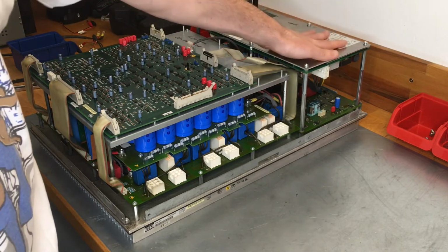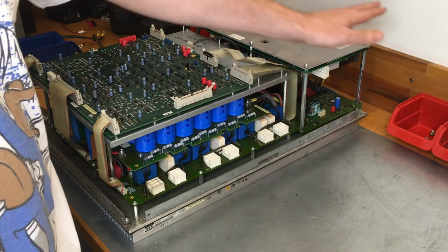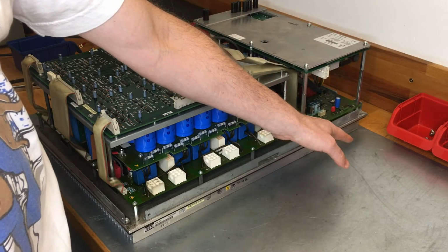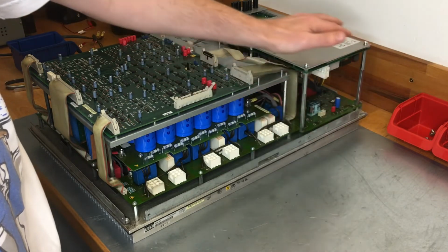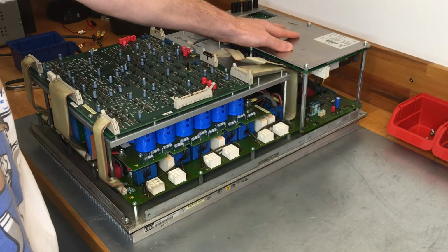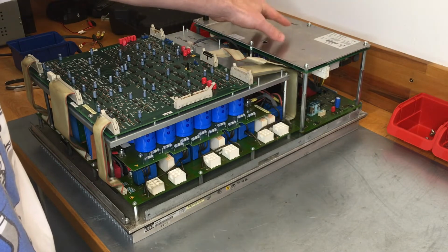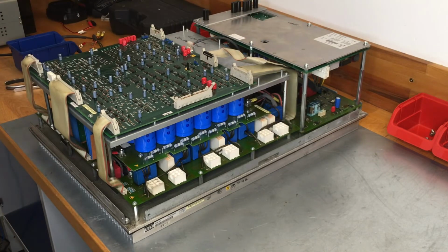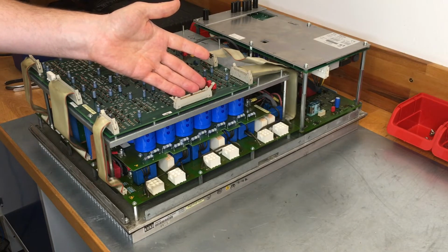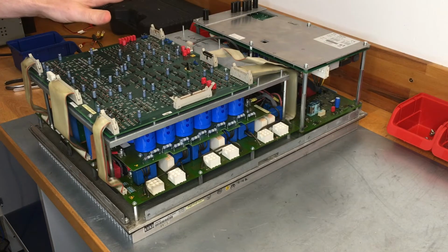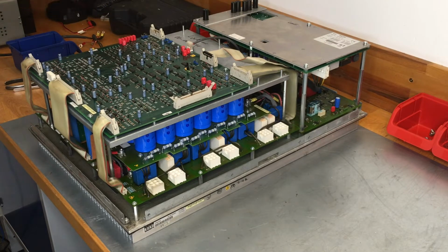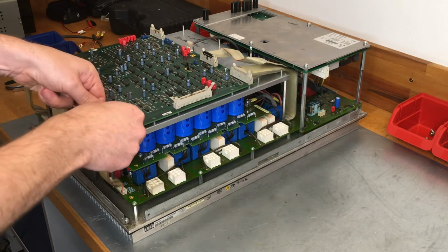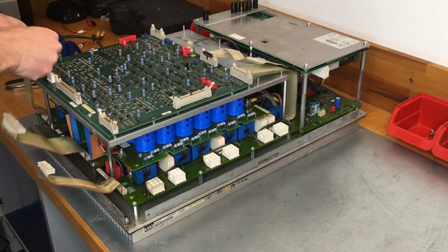I have already indicated that there are two power supplies in the upper part of the module. The high voltage power supply at the bottom that produces the DC link voltage, and the low voltage power supply at the top that produces a whole range of different DC voltages to operate the rest of the electronics. Up here you can see the so-called logic board that establishes the communication to the industrial PC, monitors the entire function of the module, and establishes the PWM signals for the individual driver cards. I have done some preparations so that I can remove the logic board relatively quickly to give you a look at the parts underneath.